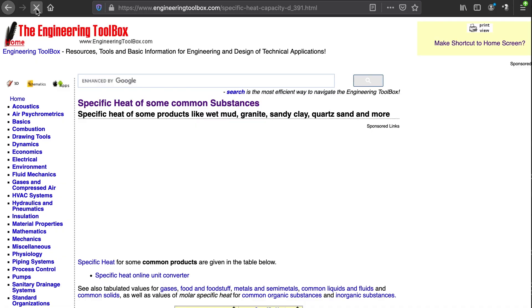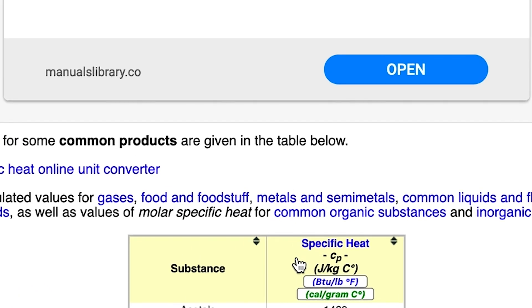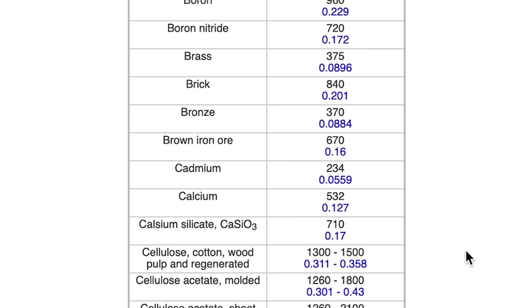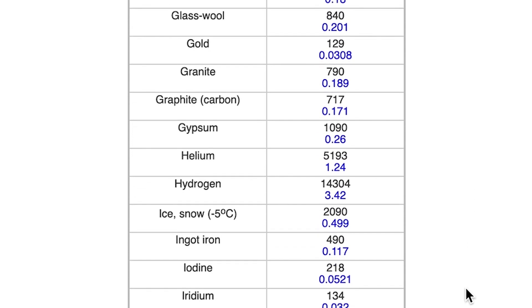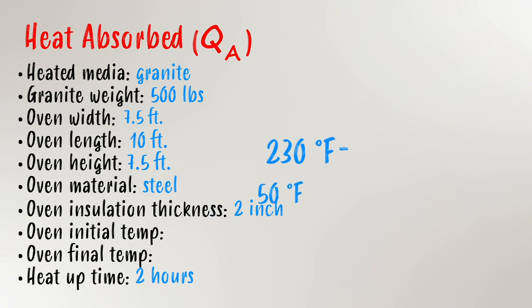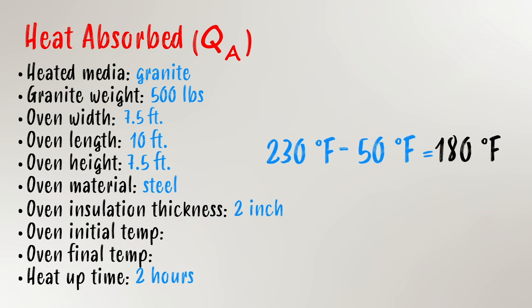Now we can determine needed values and convert to appropriate units. For this batch oven scenario, we need to determine the specific heat of granite and the temperature rise. Specific heat values can often be found online at helpful websites like the Engineering Toolbox, where you can find specific heat values for numerous materials — just make certain the values are in the correct units. Looking online, we determine that granite has a specific heat value of 0.189 BTUs per pound per degree Fahrenheit. Solving for temperature rise is simple: final temperature minus initial temperature — so 230°F minus 50°F equals a delta T of 180 degrees.